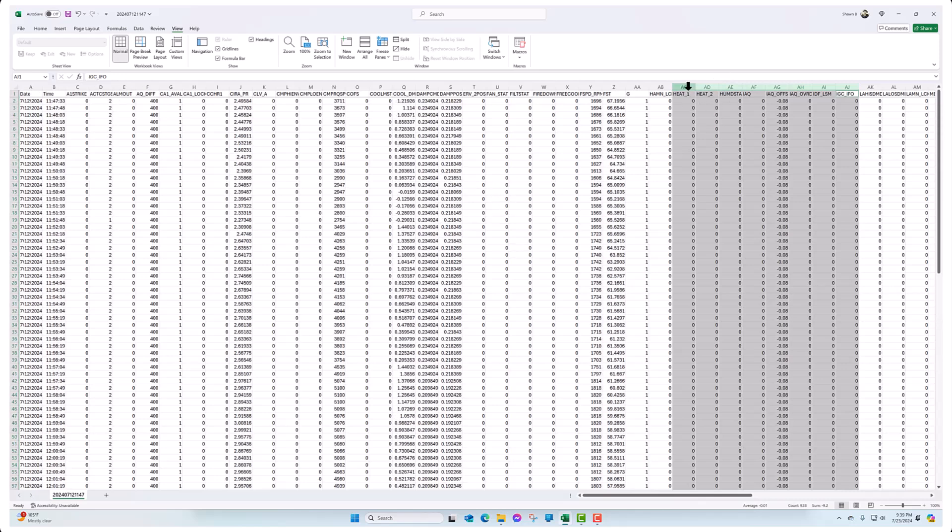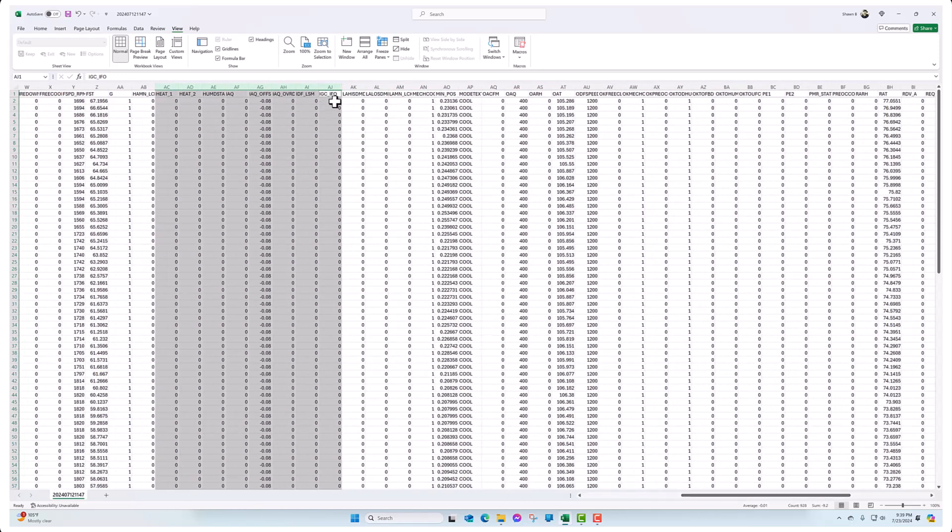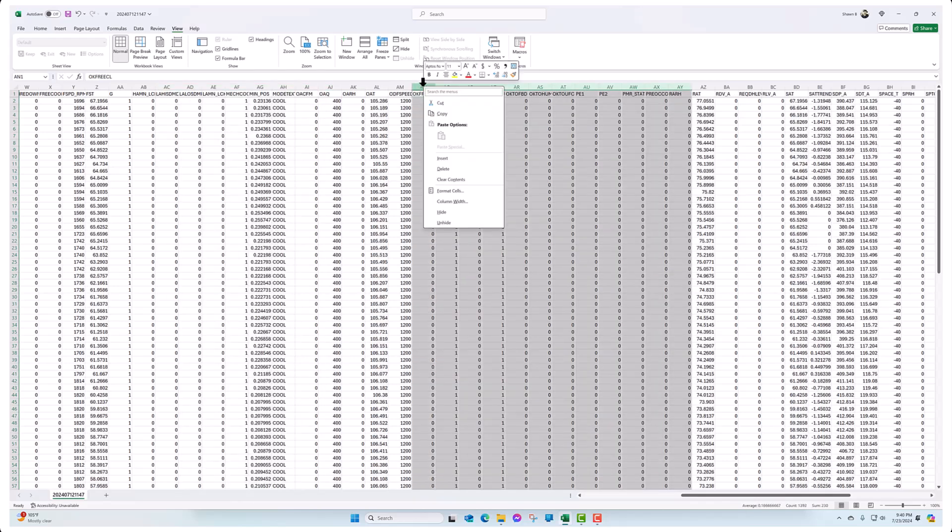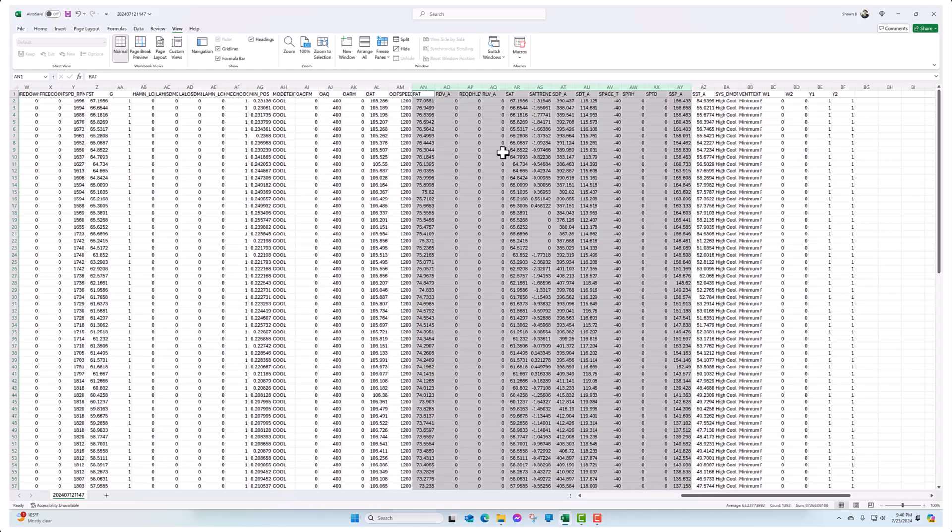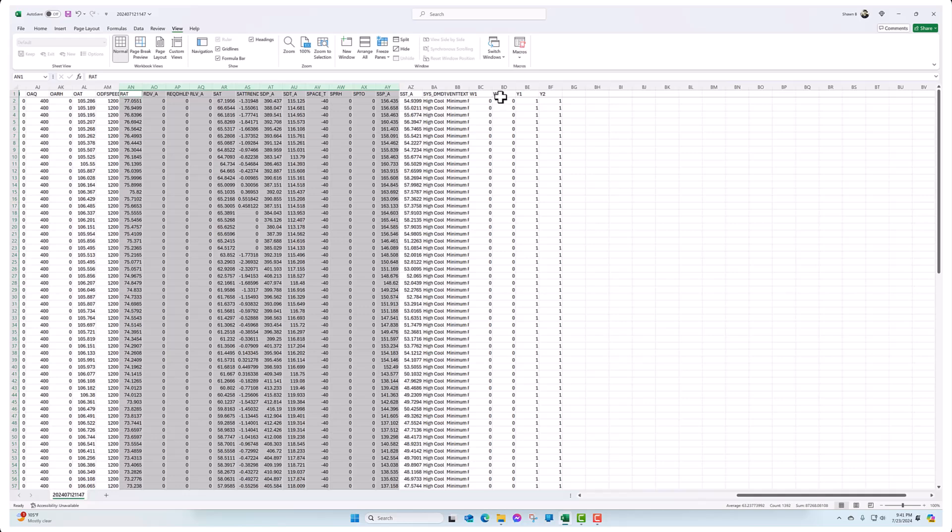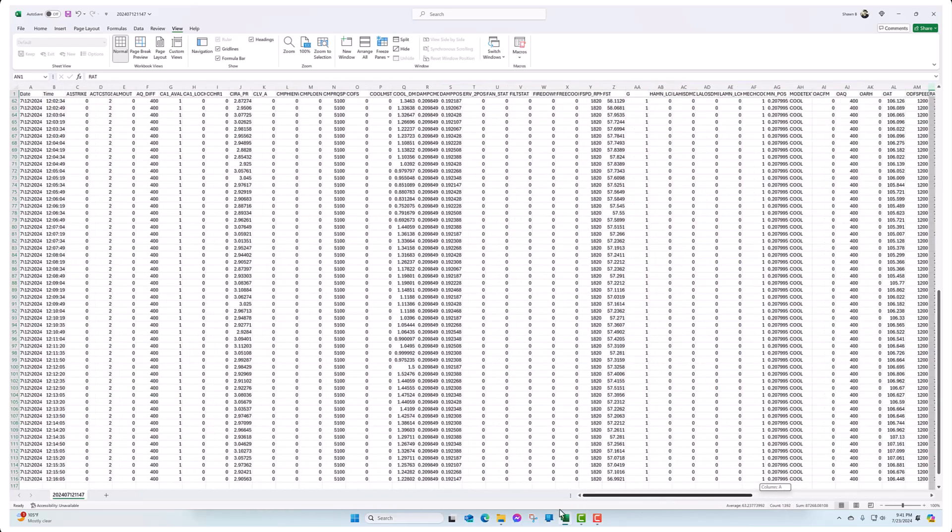So I'm going to start getting rid of things that I don't really need. I'm not looking at any heat. Here is the IGC IFO. That's how it knows if the gas lit or not, because it tells it to the IGC board to activate, giving it a W1 signal. And then you have a couple minutes it should light and then you get the delay and the fan signal should come out of the IGC board. And that's how it knows that the heat fails. So that's what that input is. We don't need that. Okay for free cool. We don't need any of that for what we're looking at. So I delete that stuff out. And I've modified these before where I kind of just move things where I like them. Like right here it puts W1, W2, Y1, Y2. Of course you have your, there's your inputs. So I would sometimes move them all the way over here to the left and kind of make it a left to right thing sometimes. And I've kind of really tried to study these before. But we don't need to do that today.